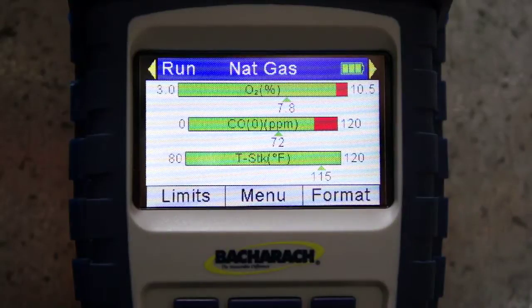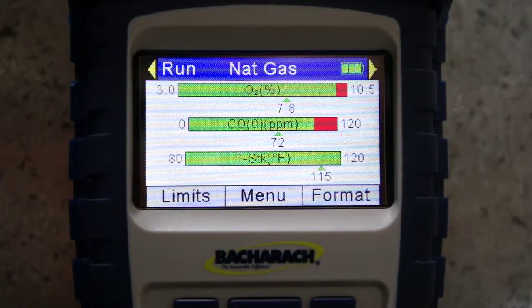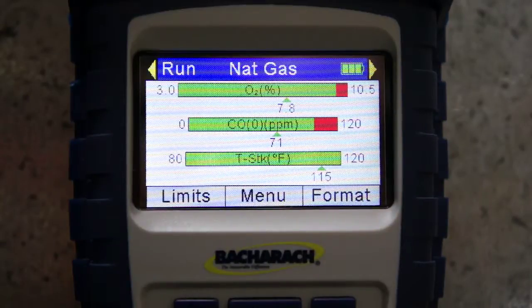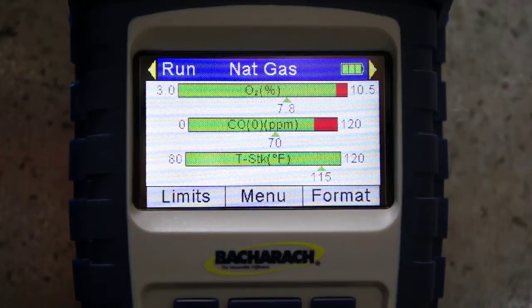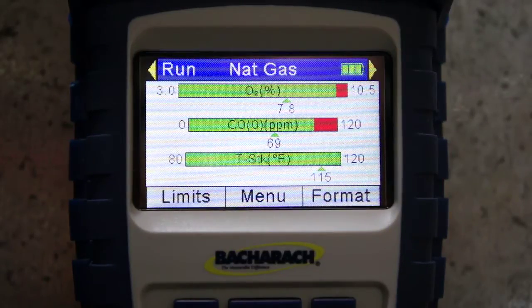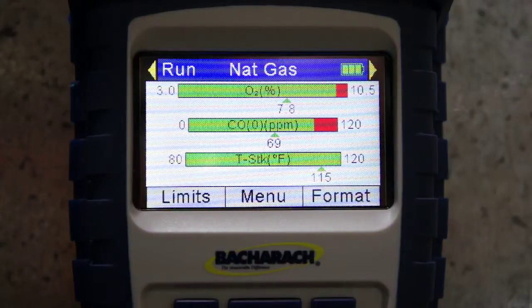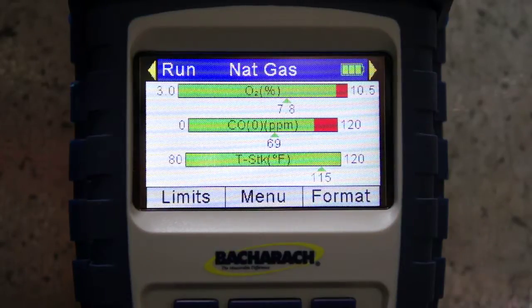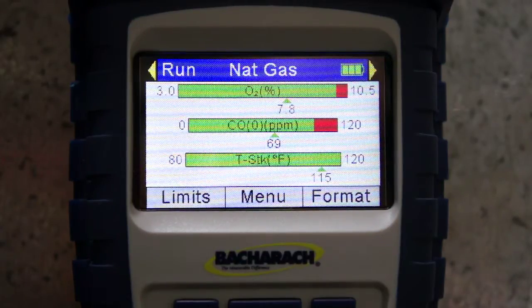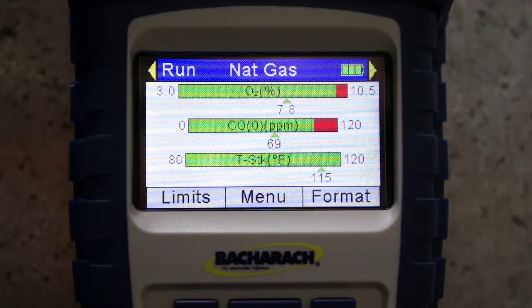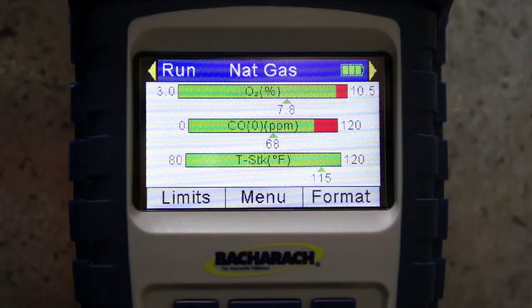So now you can see if I'm a company owner and I say, okay guys, I want you to measure these things. I want to make sure that your O2 is between 3 and 10%. I want to make sure your CO is configured so that we're not above 100 parts per million. I want to make sure on a 90 plus furnace that stack temperature is between 80 and 120. I can tell the guys exactly where to configure it, and as long as the arrows end up in the green, I'm good to go. I can walk out the door and know that my system is safe.